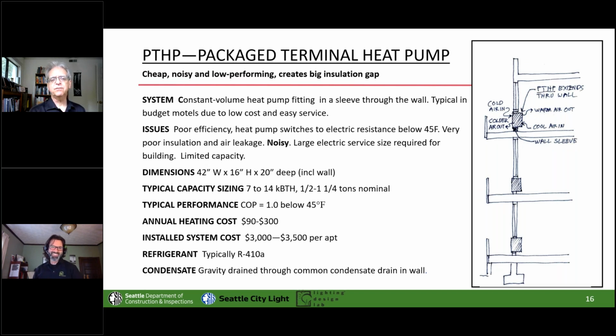So here's my least favorite of all the options, and the new rules will make it harder for these to run, because as I was just saying about that last one, you need a system that keeps running on compressor only down to freezing, and then runs as a compressor and electric resistance supplement below freezing, which most of these can't do. There are some, but if you've ever stayed in a budget motel and you had a unit on the wall that roars to life whenever it needs to do some heating or cooling, and then does a little clatter thing at the end, that's your package terminal heat pump.